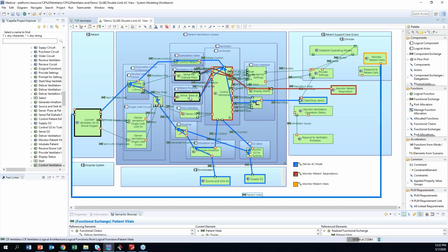Sure. Well, maybe I can go in a little bit of a different direction. In med device, we're required to be compliant with ISO 62304, which is really software lifecycle management for medical device software. And in the standard, we're required to provide a software architecture document. This is discussed in the document as a hierarchical model. They talk about systems and items and units, so it's sort of a nested bill of materials kind of view of it.